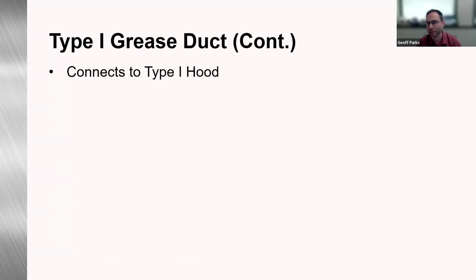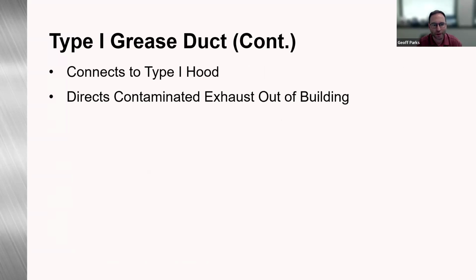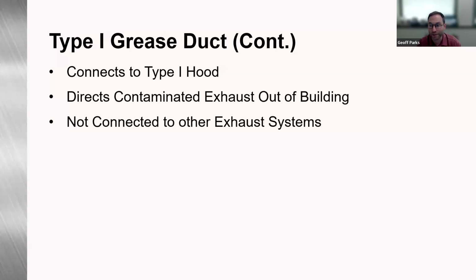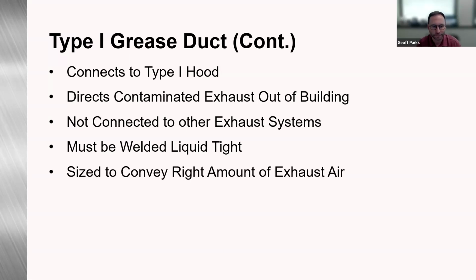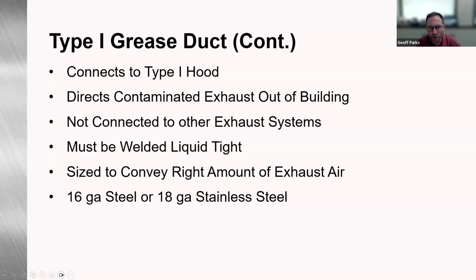Type 1 grease ducts, it connects to a Type 1 hood. It's going to direct the contaminated exhaust out of the building. This is not going to be interconnected with any other exhaust system. Again, must be welded liquid tight, sized to convey the right amount of exhaust air. You want to make sure that the minimum feet per minute is going to be per the codes. I think it was 500 feet per minute, if I'm not mistaken. And then again, our construction options, 16 gauge steel or 18 gauge stainless steel, NFPA, and the International Mechanical Code.